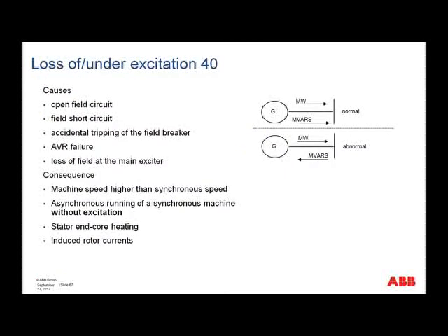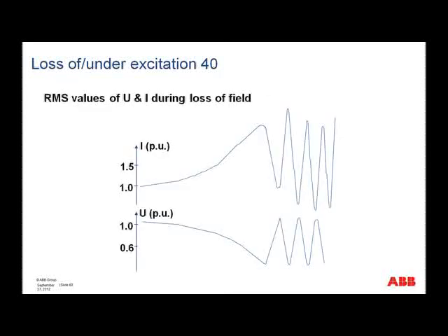Loss of or under excitation, there are a number of causes for this. And the consequences, of course, is that the machine speed can be then higher than synchronous speed. This is for a generator. If it was a motor, it would be the opposite. And really the reason for this is that we require the rotor current to get the coupling. So what you could say then is we have this asynchronous running of a synchronous machine without excitation. And you can get stator end-core heating, you can get induced rotor currents, and this is what would be the consequence of this.